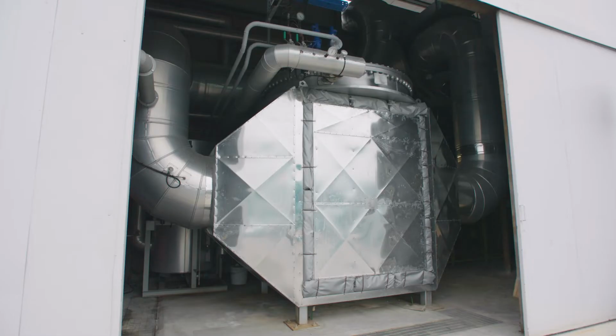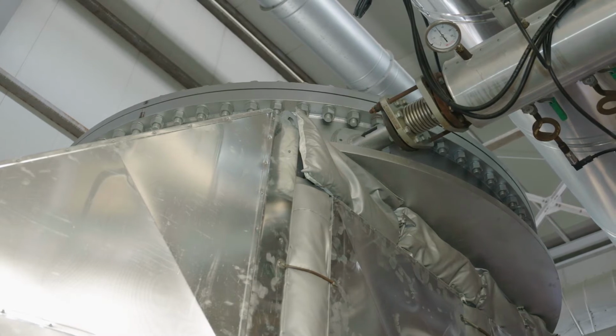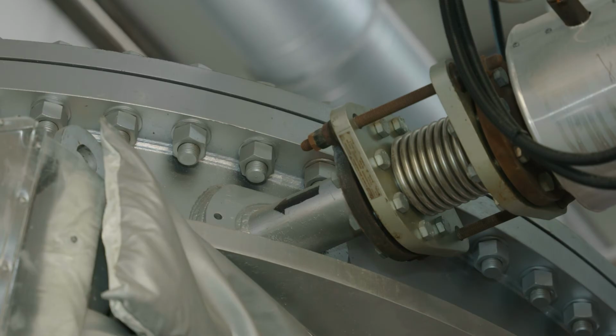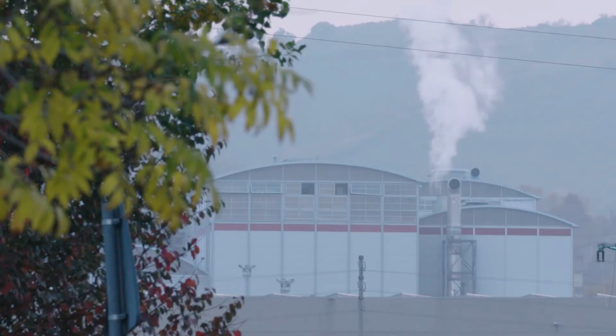The exhaust streams straight from the kilns contain both hydrofluoric acid and particulate, and have high temperatures and flow rates that could possibly damage the system. So the engineers had to find the right setup and select the right materials for the heat pipes so that thermal recovery would work efficiently inside the plant's environment and within the applied temperature range.